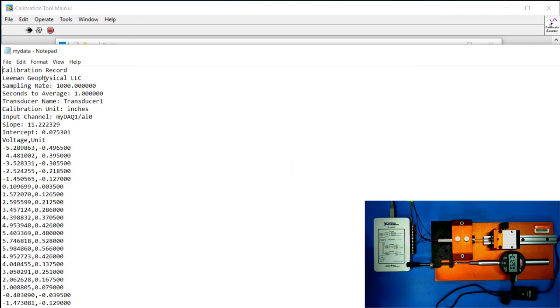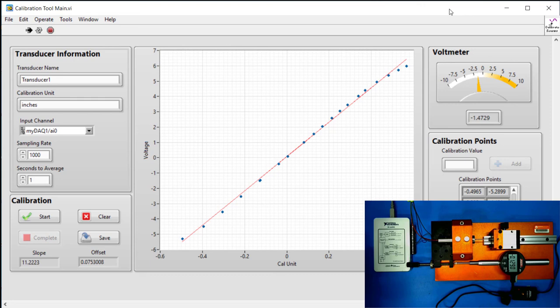As you see, it tells you it's a calibration record, the sampling rate, the seconds that you averaged, the name of the transducer, the unit, what channel it was calibrated on, the slope, intercept, and then all of the raw calibration points. So as you can see, it's very easy to set up and use the DCDT calibration apparatus, and you can calibrate transducers in just a couple of minutes.